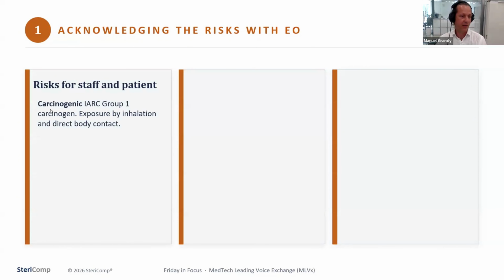So first of all, acknowledging the risks with EO. There are definitely risks for staff and patient. Okay, it's carcinogenic. It's an IARC group 1 carcinogen, which means that there is no doubt about it, that it's carcinogenic by exposure, by inhalation, and with direct body contact. So it means that in the facility and surrounding areas, there is potential risk if it gets into contact. And the direct body contact is then for the patient. There is a residue of EO on the medical device, and it's also a risk that you must address, okay?